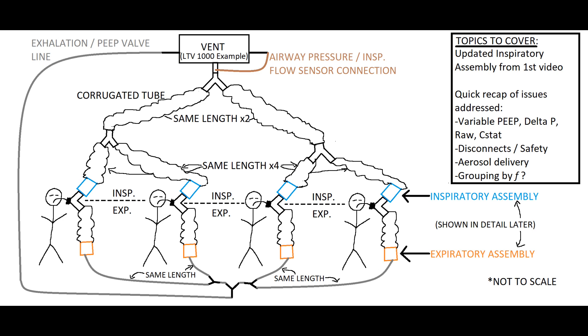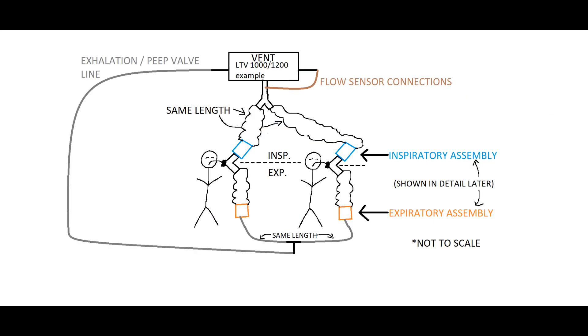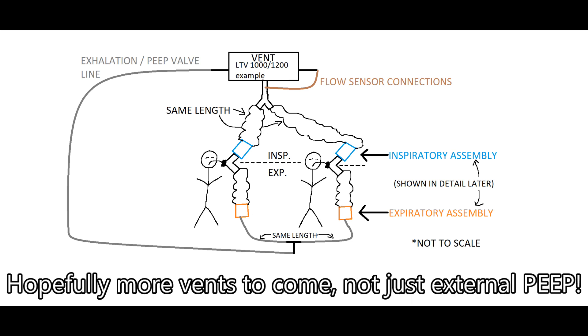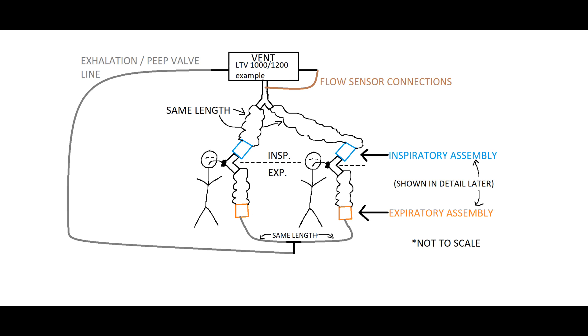The biggest change is going to be cutting the setup down from four patients to two patients. We figured four is going to obviously add lots of complications, so we tested with two. Theoretically, you could expand it to three or four, but even if it works with just two, that potentially doubles the number of available ventilators if we can figure out a way to get this to work with every single vent.